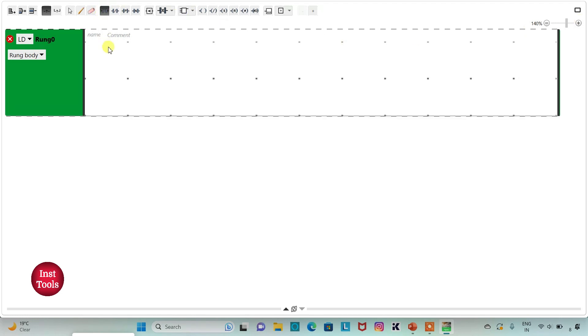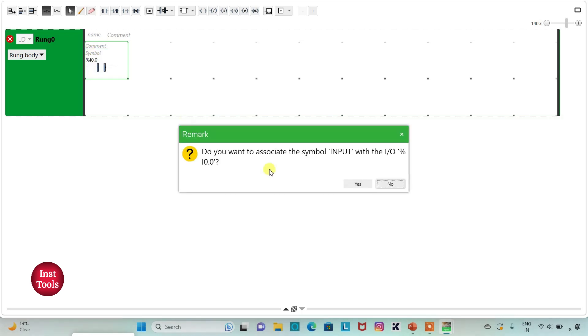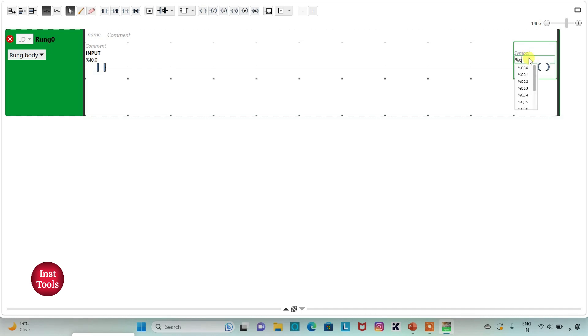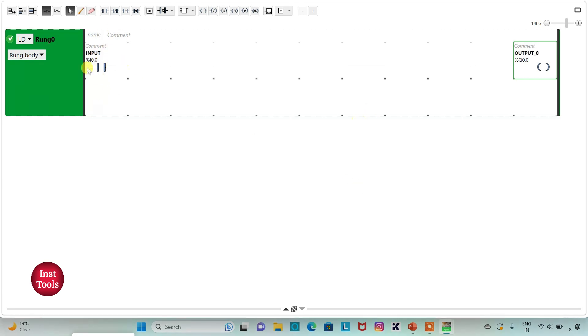Firstly, I will insert a normally open contact and assign the address I0.0 to it, with the symbol 'switch' or 'input'. When input is true, I will insert a coil and assign the address Q0.0 to it, with the symbol 'output 0'. When input is turned on and is true, output 0 will be true. When input is false, output 0 will be off.